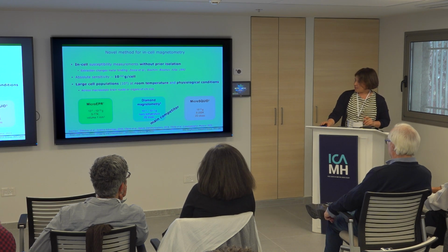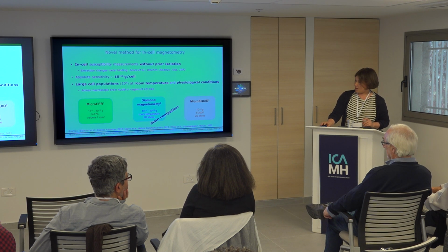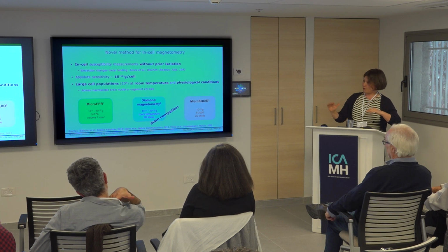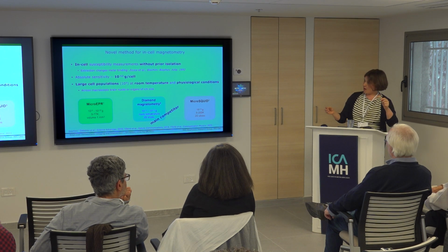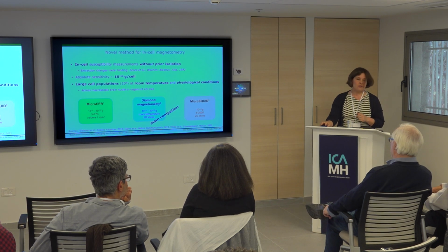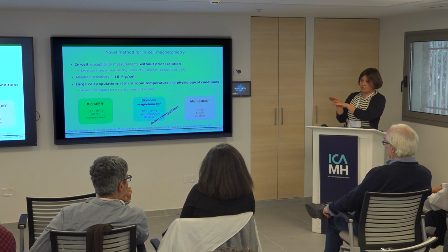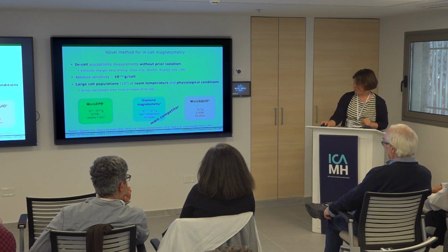We calibrate it in two ways. First of all, our iron measurements are calibrated with a standard and also from first principle calculation. We actually also compared two different methods, PIXE and XRF, and they compared very well.